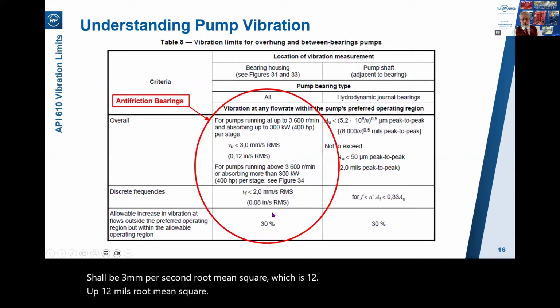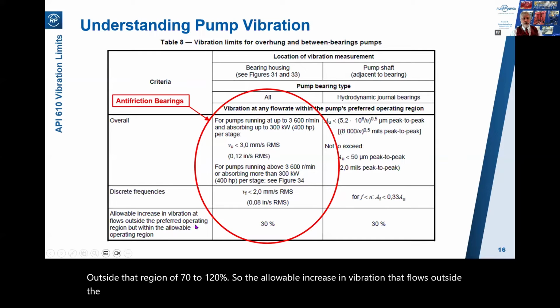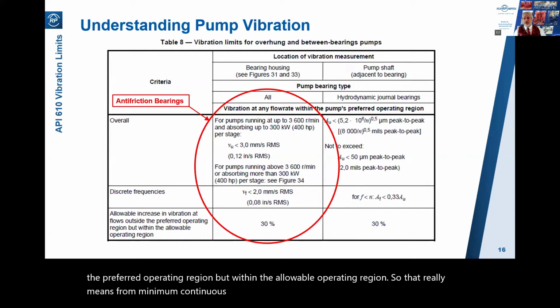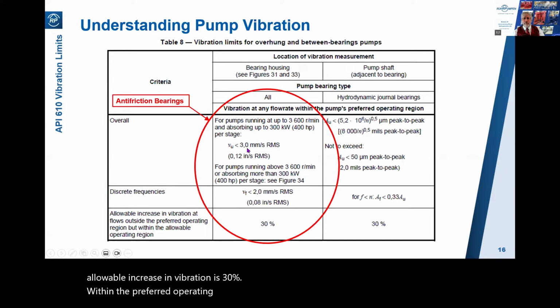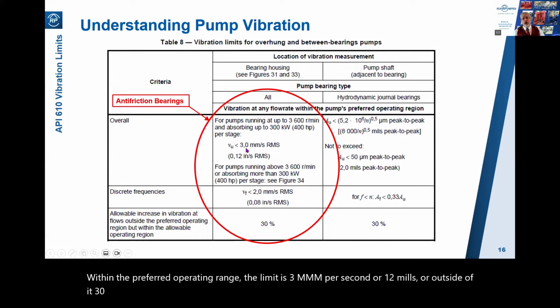Outside that region of 70 to 120%, so the allowable increase in vibration at flows outside the preferred operating region, but within the allowable operating region, so that really means from minimum continuous flow to 70% of best efficiency point flow, it says the allowable increase in vibration is 30%. So within the preferred operating range, the limit is 3 millimeters per second, or 12 mils, or outside of it, 30% more, which is 3.9 millimeters per second, or 0.16 mils.